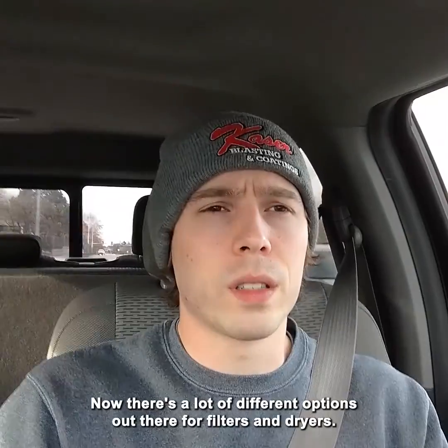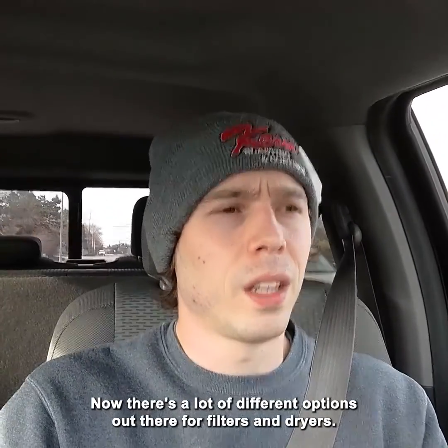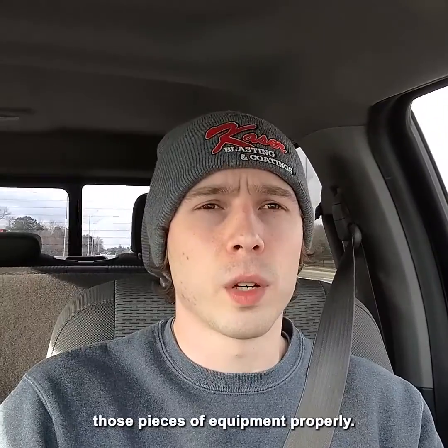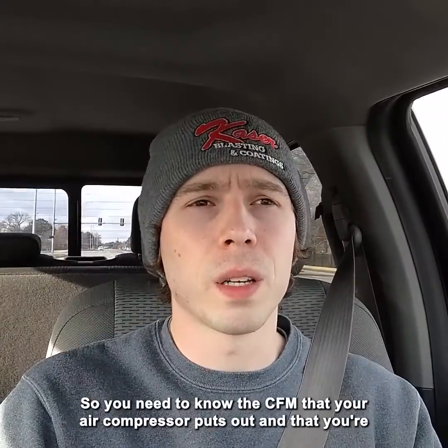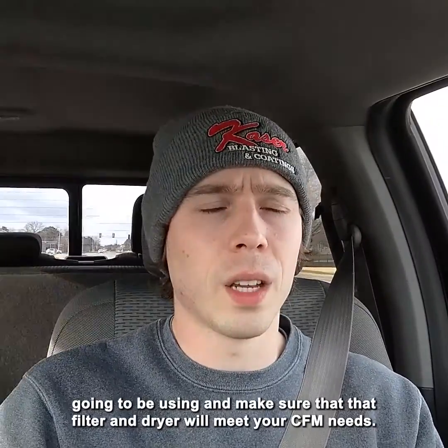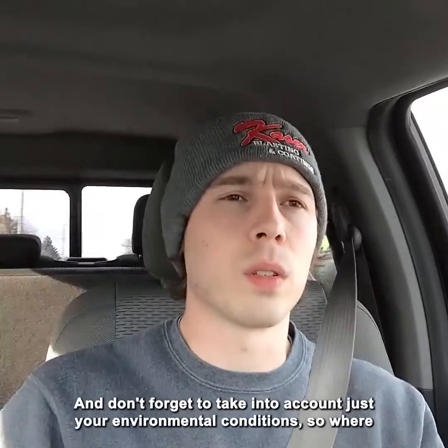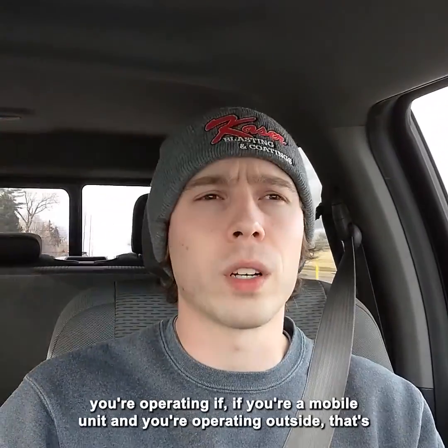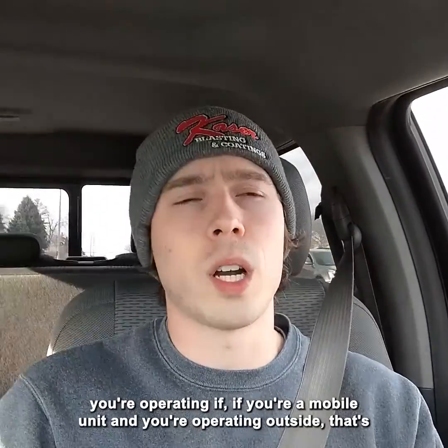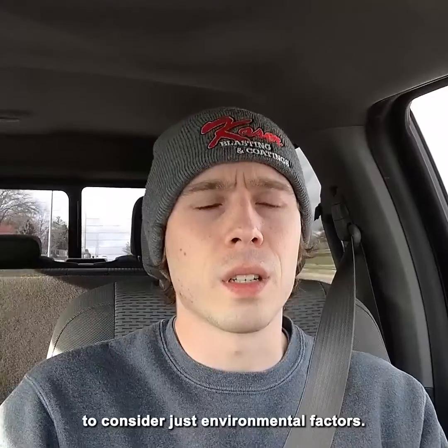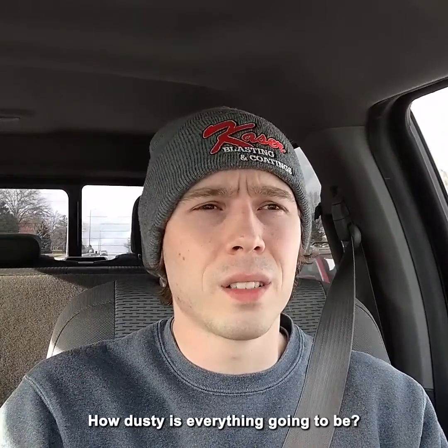Now there's a lot of different options out there for filters and dryers. All I can say is the most important thing is to size those pieces of equipment properly. So you need to know the CFM that your air compressor puts out and that you're going to be using, and make sure that the filter and dryer will meet your CFM needs. And don't forget to take into account your environmental conditions. Where you're operating, if you're a mobile unit operating outside, that's going to be different than being inside of a building, because you have to consider environmental factors. How dusty is everything going to be?